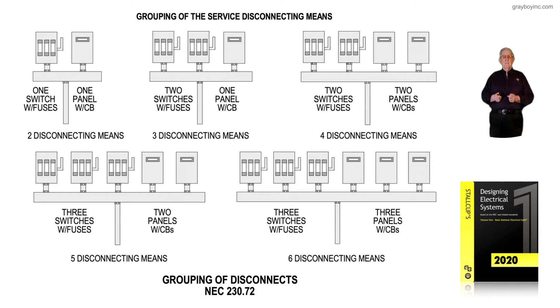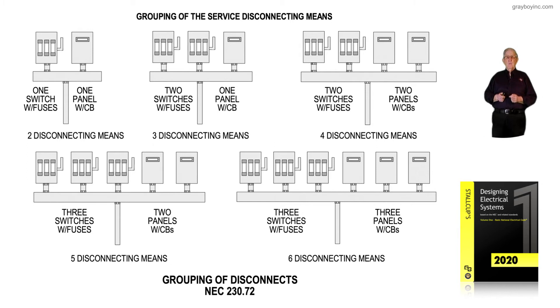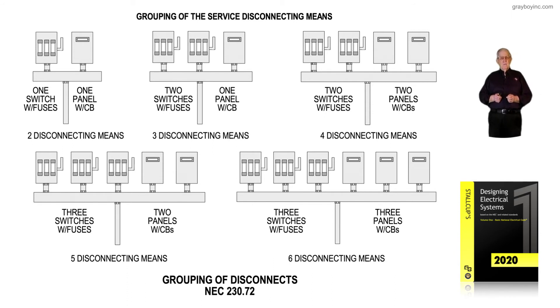It's up to the designing engineer or the installing contractor, operating within the authority granted by state, county, or city ordinances. To the right of the illustration, we're using the maximum number of disconnects — two to six, and here we have six: three fusible switches and three main circuit breakers. You can walk up to that equipment and disconnect it with six throws of the hand, as required in 230.71 and 230.72. This figure 6-37 simply illustrates a grouping of disconnects from two to six.